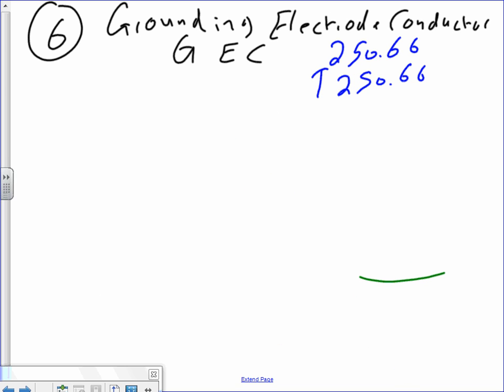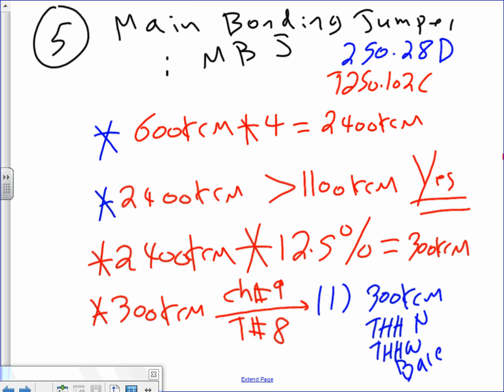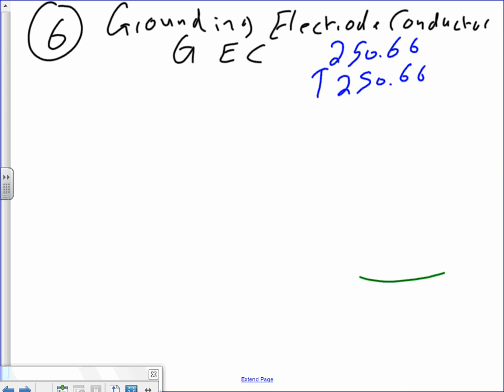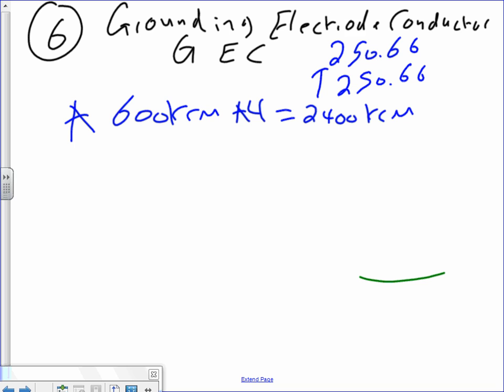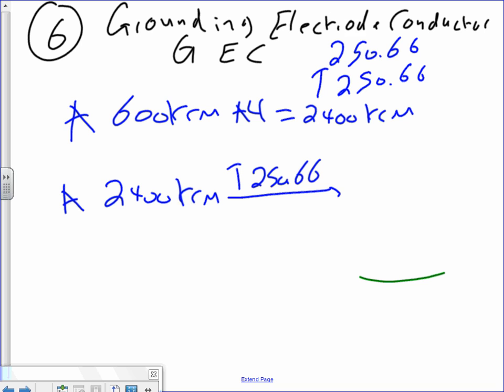Okay, gentlemen. Grounding electrode conductor. Let's do grounding electrode conductor. Change that table to... Okay. Any question about the main bonding jumper? Good. Grounding electrode conductor. Hold your horses. For grounding electrode conductor, you do the same math. The same math. 600 kcm times 4 equals 2400 kcm. Then you take the 2400 kcm, take it to table 250.66. Different table. Only this year, guys, they made a different table. It used to be one table. Remember that one that got born this year? 250.102(C) got born. It's actually, we cloned it from 250.66.